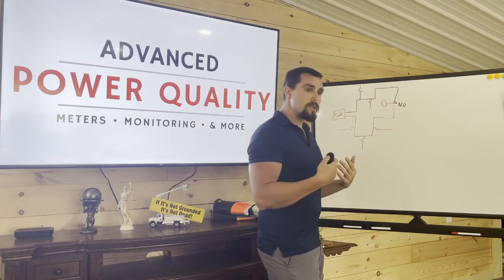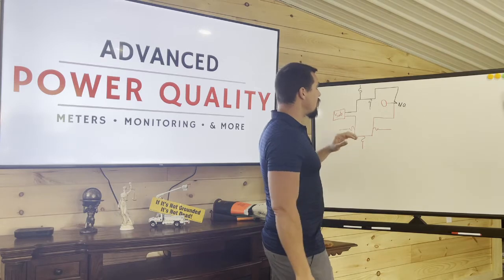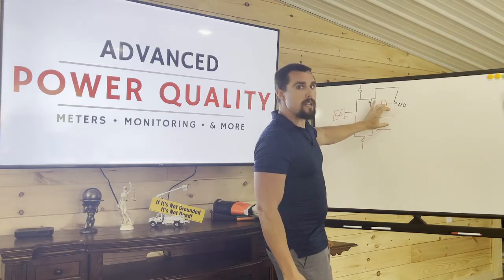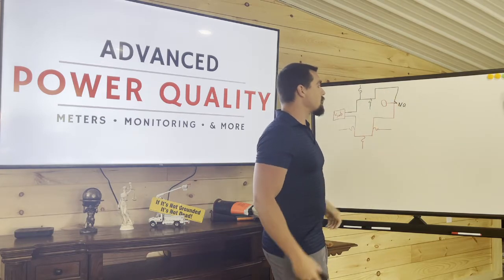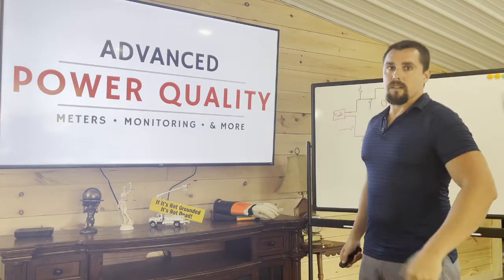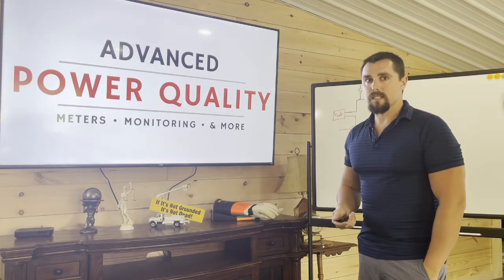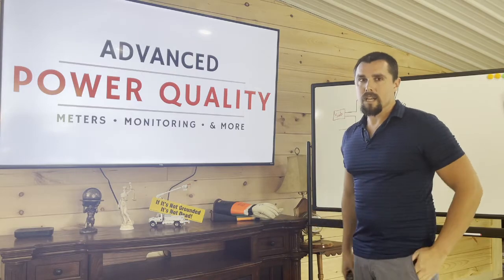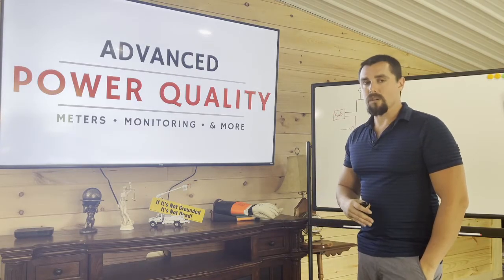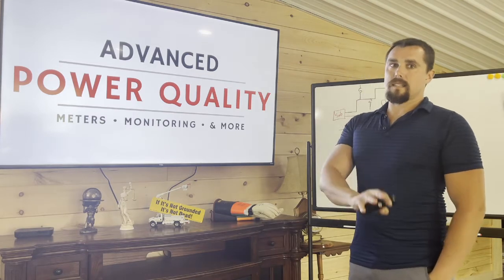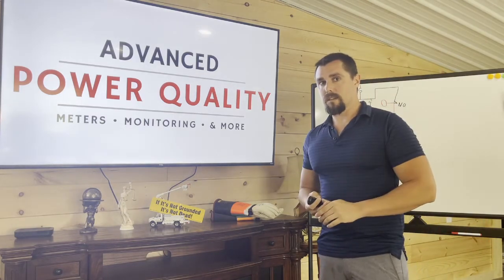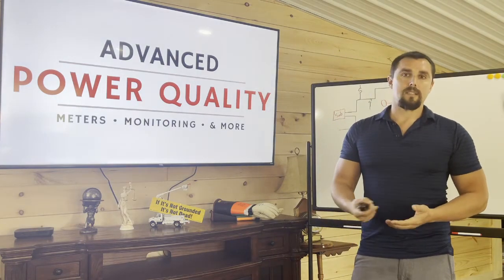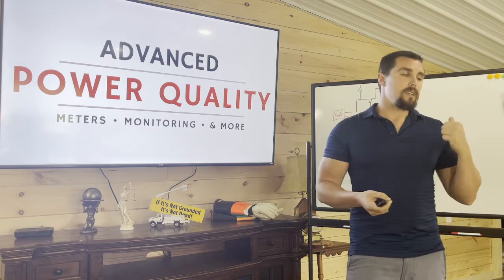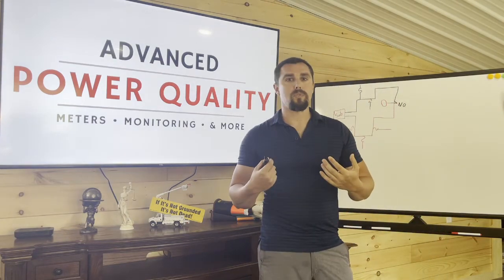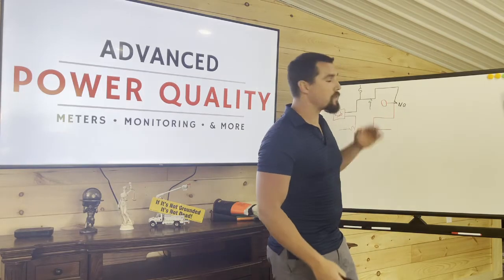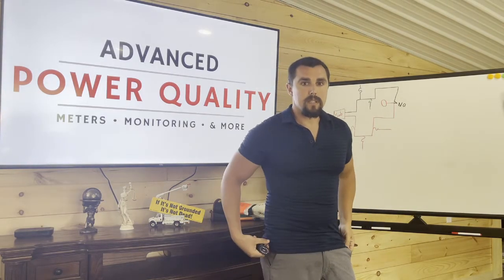Now what this does is create a voltage imbalance issue. So here, the customer may not be seeing a voltage imbalance. Whenever they switch over, the customer's seeing a voltage imbalance. And as most of our customers know, voltage imbalance is amplified on the current side. Typically, we want to see well below 4% voltage imbalance. That's if the customer is very load balanced on their side. Now, if the customer's load imbalance is above 10%, essentially the voltage imbalance needs to be limited to less than 1%. If you have a fuse blow on a capacitor bank, it most likely is going to be above this.